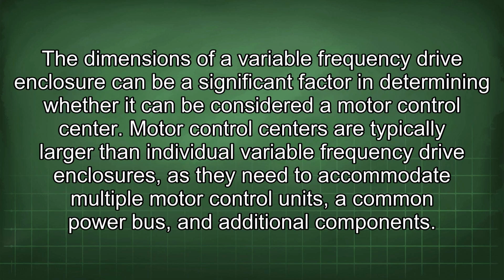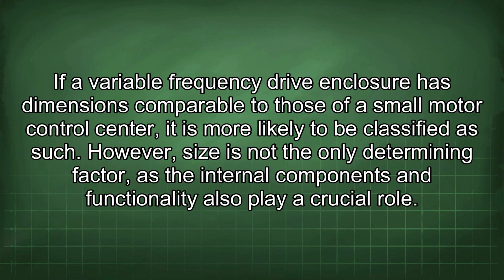The dimensions of a variable frequency drive enclosure can be a significant factor in determining whether it can be considered a motor control center. Motor control centers are typically larger than individual variable frequency drive enclosures, as they need to accommodate multiple motor control units, a common power bus, and additional components. If a variable frequency drive enclosure has dimensions comparable to those of a small motor control center, it is more likely to be classified as such. However, size is not the only determining factor, as the internal components and functionality also play a crucial role.